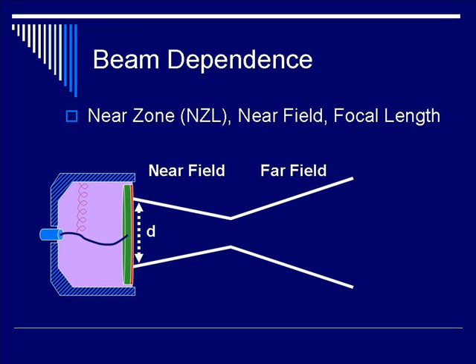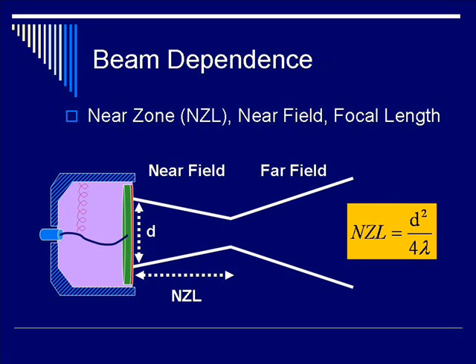The beam diameter, D, is the measurement that can be varied across the beam profile. At the near zone length, NZL, which is known as the focal length, D equals the minimum beam diameter or beam width. NZL is defined as D squared over 4 lambda, where D is the transducer diameter and lambda is the wavelength of the ultrasound beam.